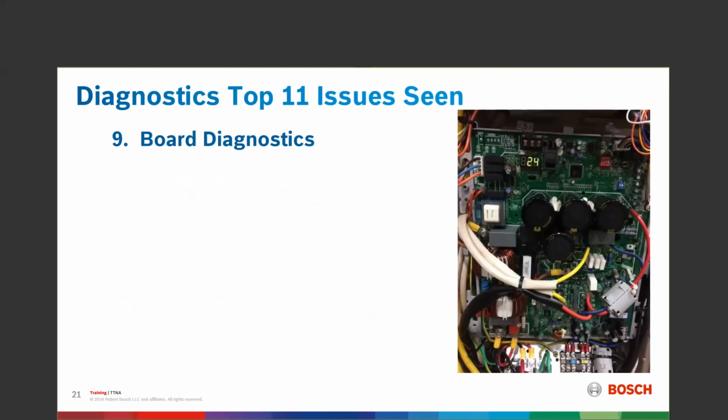Board diagnostics. So the board has been pretty good. Safety is a major concern, guys. I can't talk enough about safety. One of the things that keeps coming back to me was a contractor up in Canada who went in to service a heat pump. It wasn't ours. It's just a story that's told. We know with resilient mount motors, there's a rubber block that isolates the motor from case ground. There's a ground wire that normally goes from the motor itself to the motor housing or the fan housing. The ground wire was missing. The guy put a hand on the motor for some reason and touched the housing. He's no longer with us today.